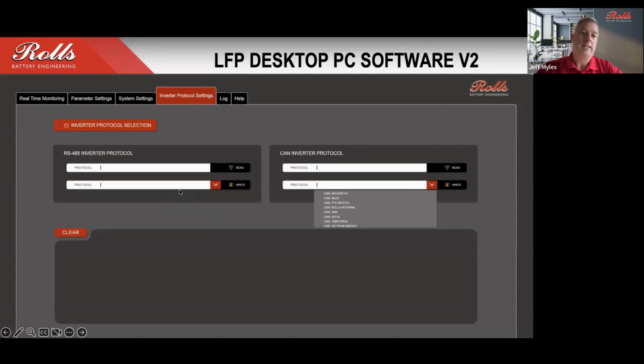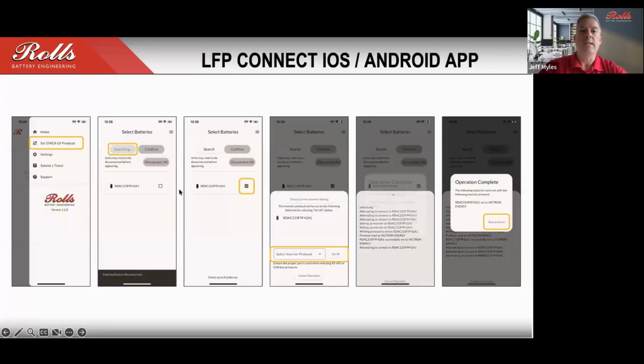To do that, each one of the batteries is going to have a Bluetooth address sticker, and that's going to essentially identify that unique battery. So when you're stacking these and assigning the protocol, you would, in this case, connect to the primary battery, and that would assign the protocol specifically to that battery. But in the case of using the Connect app, you'll be able to connect to any one of the batteries in the stack.